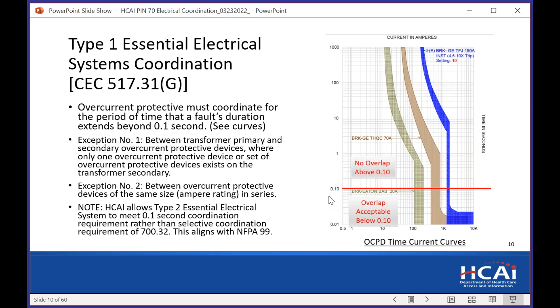So we're going to allow overlap, and it's done with the idea that if you had a bolted fault short, we're going to take the risk that you're going to take down more than just the localized equipment. And so it's a trade-off. It's a trade-off in design. And just to be clear, we're just adopting the national standard. So in this case, that's how the NEC is written, and we take no exception to that allowance.